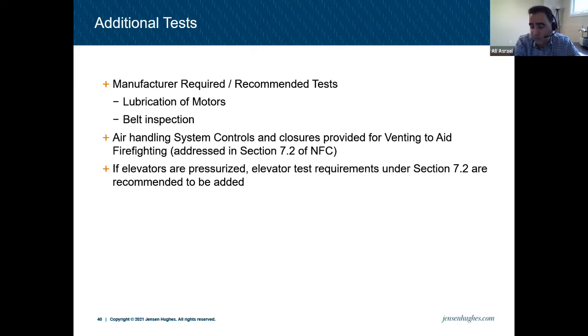We're doing 7.3, but this is addressed in 7.2. 7.2 of the fire code is saying venting for firefighting has to be tested. So when you're doing a 7.3, I think it makes sense to include it in the same document and just do it, because I bet you nobody does that either.